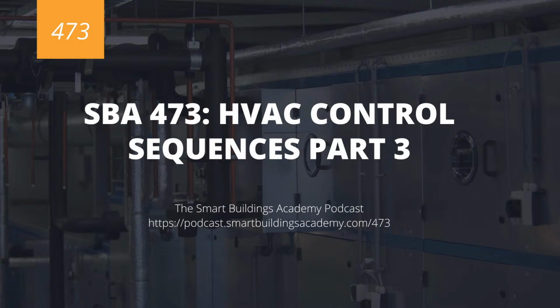But when we're dealing with a single path constant air volume unit, we are typically, as I mentioned, varying our discharge air based on space reset. And so we typically will have some form of reheat as well. And that reheat will typically be used both for dehumidification sequences as well as just for controlling discharge air. And like I said, we'll talk about those sequences in a second.